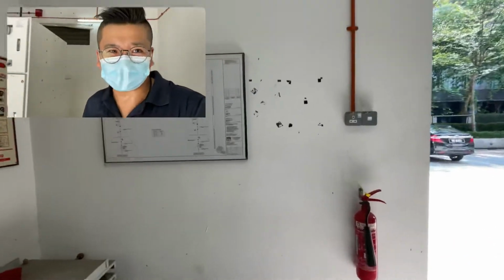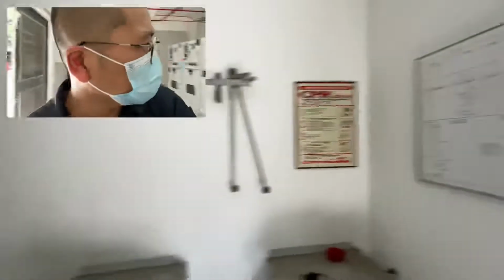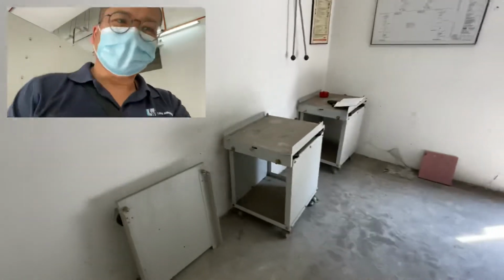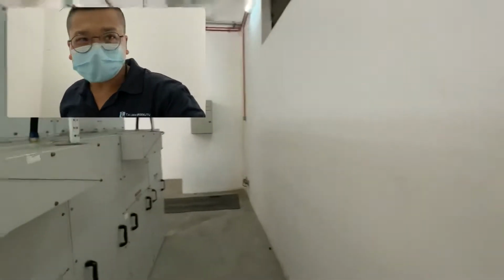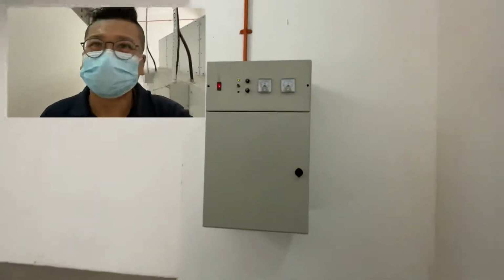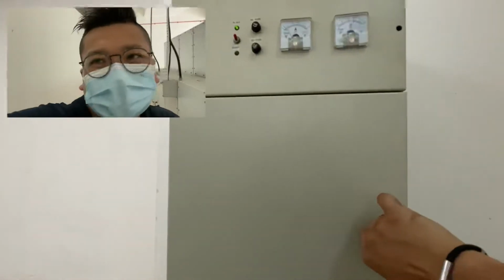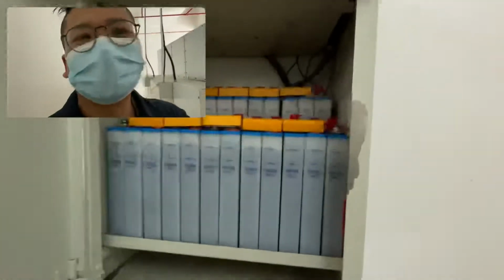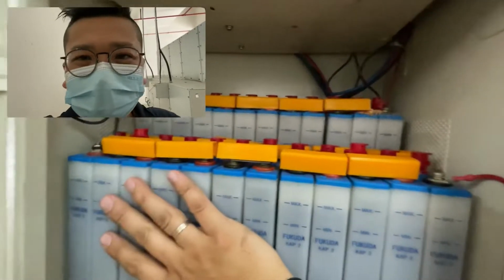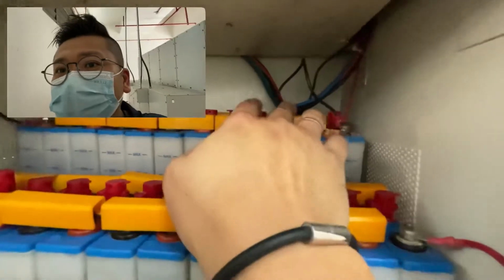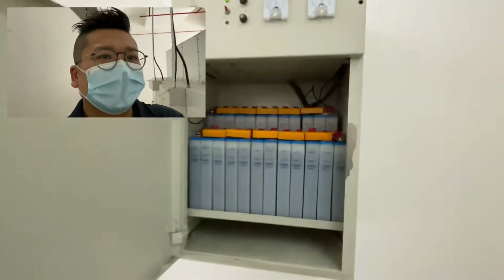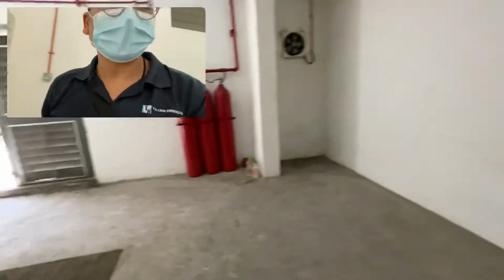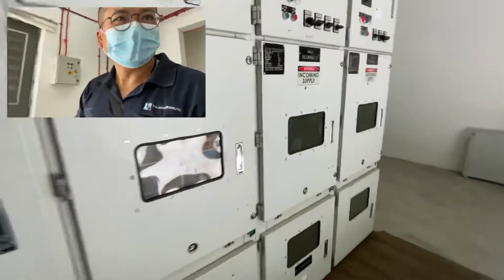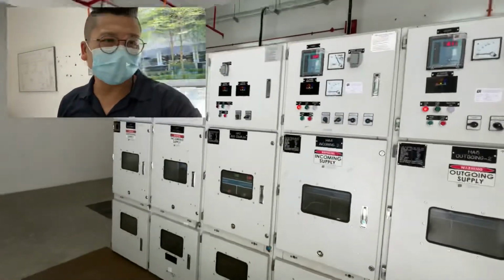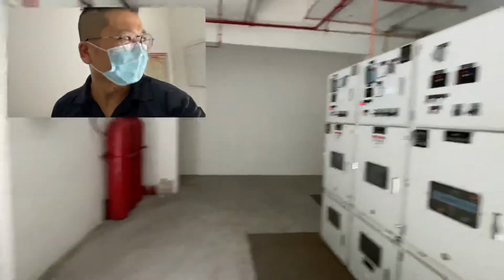Oh, the borang B is not affixed here. ST borang B. Okay, the switchgear trolley is here. Let's check the tripping unit. Okay, in good condition, no overcharge. Termination is clean. There's some dirt here. Okay. Electrolyte level is okay. Okay, overall is in good condition.